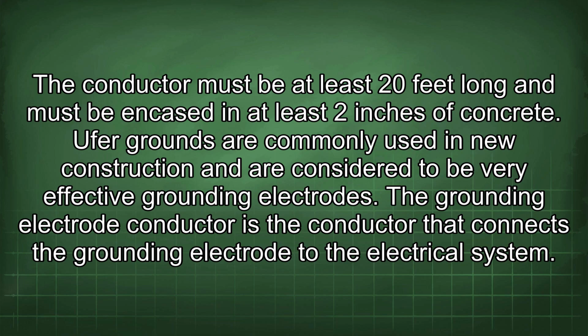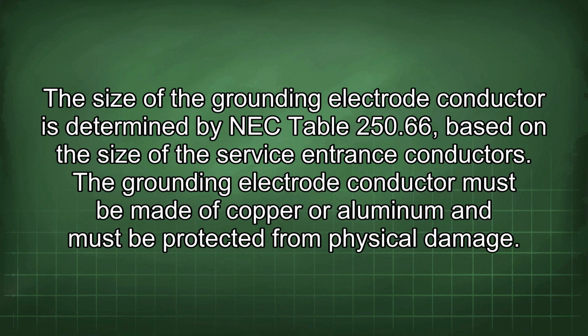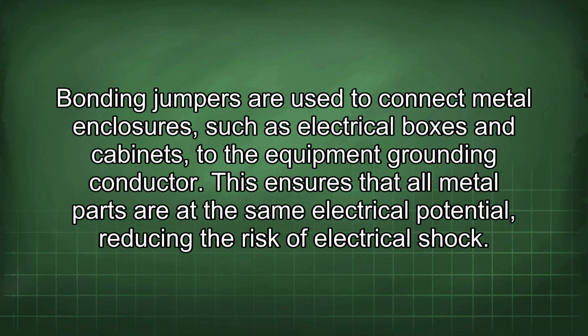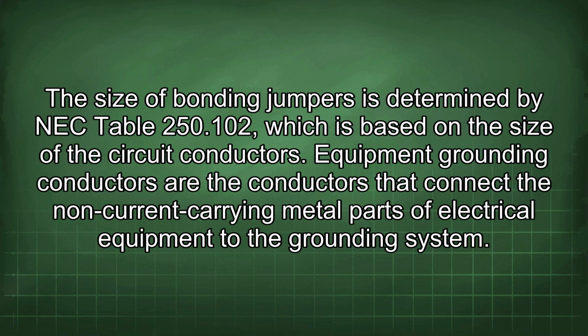The grounding electrode conductor is the conductor that connects the grounding electrode to the electrical system. The size of the grounding electrode conductor is determined by NEC Table 250.66, based on the size of the service entrance conductors. The grounding electrode conductor must be made of copper or aluminum and must be protected from physical damage. Bonding jumpers are used to connect metal enclosures such as electrical boxes and cabinets to the equipment grounding conductor. This ensures that all metal parts are at the same electrical potential, reducing the risk of electrical shock. The size of bonding jumpers is determined by NEC Table 250.102, which is based on the size of the circuit conductors.